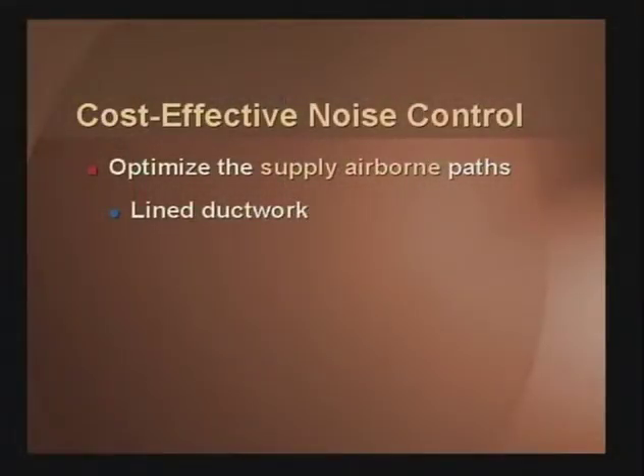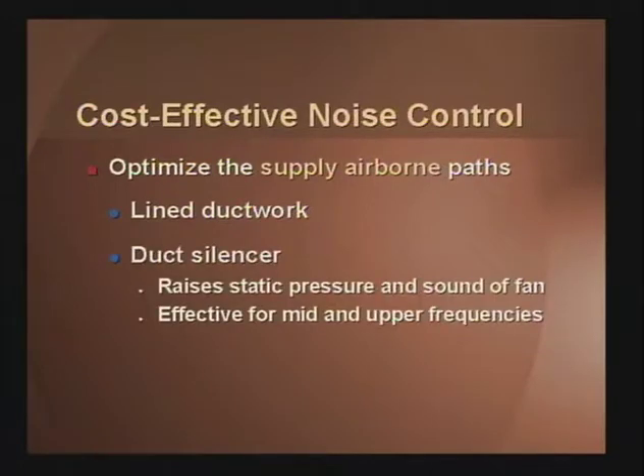Other things you can do is line the inside of the ductwork with 1 or 2 inches of fiberglass out about 30 feet, if that's allowed and approved by the parties to be. Another choice is to use duct silencers. But be careful in applying duct silencers. They should be applied generally in the mechanical room wall. And be very careful applying silencers to FC fans. Silencers increase the static pressure of the system, and on FC fans, it will increase the noise level of the fan. Silencers will take out the high frequencies, and with an FC fan you may end up with a rumblier unit than when you started. Be careful.